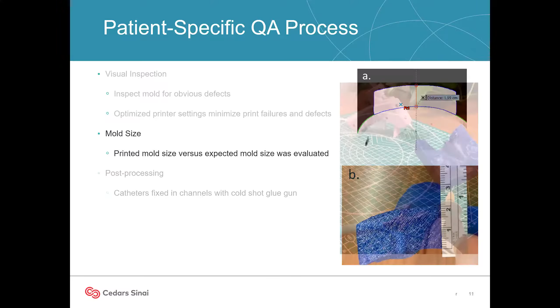And for each applicator, we do post-processing to ensure that everything is reproducible and safe. So we affix the 4.7 French catheters in the mold with a cold shot glue gun so that we don't damage the catheters. We want to make sure that they're in the proper channels and that the channel numbers are labeled so that there will be a smooth passage of the source in the correct channel when we treat the patient. We also make sure there's no rough edges or anything that could be uncomfortable for the patient. And we routinely use a Dremel just to sand down any areas that could be uncomfortable for the patient.